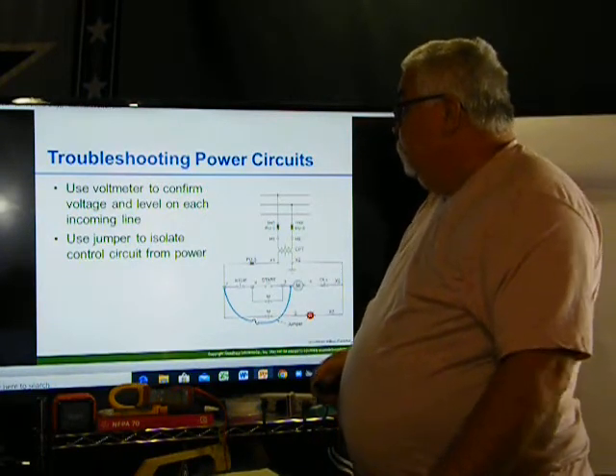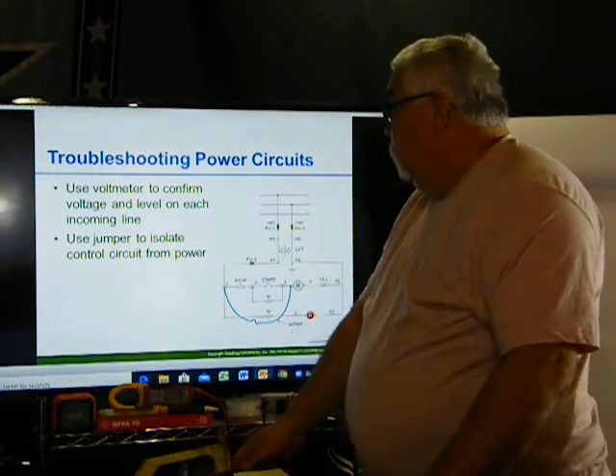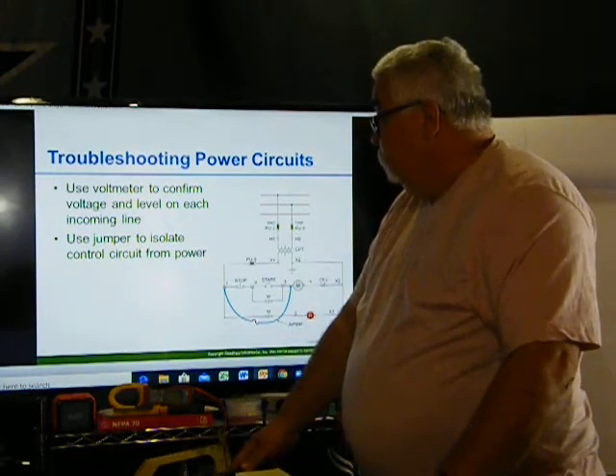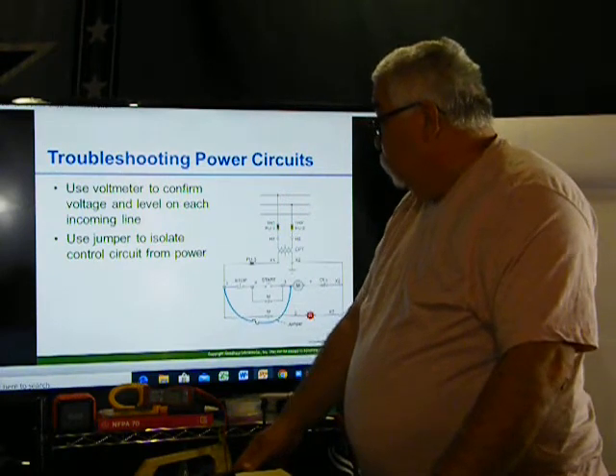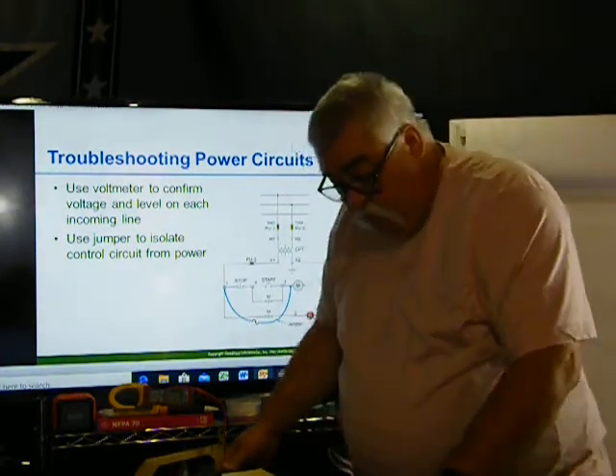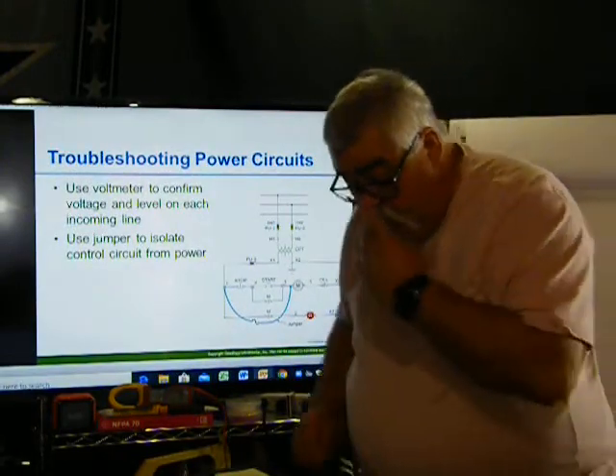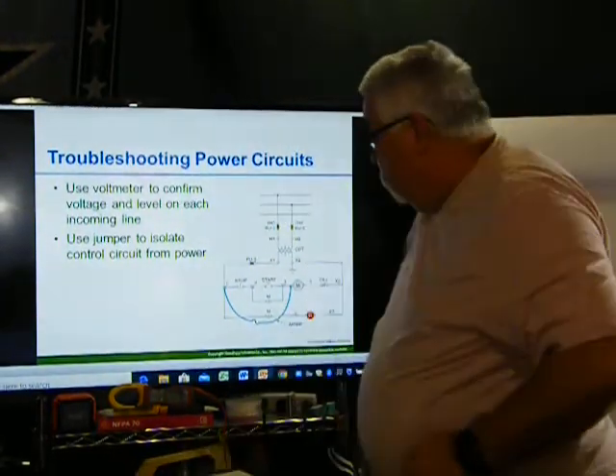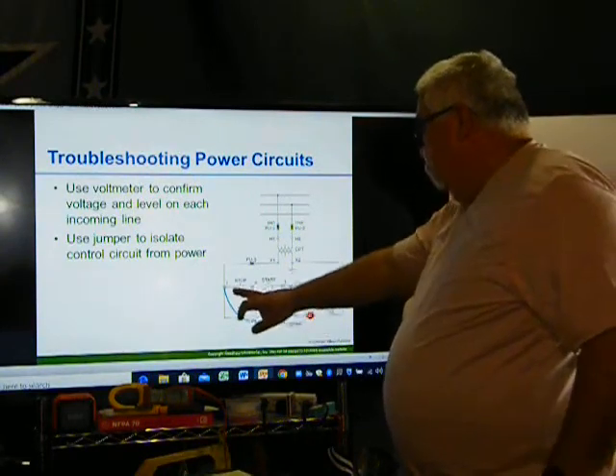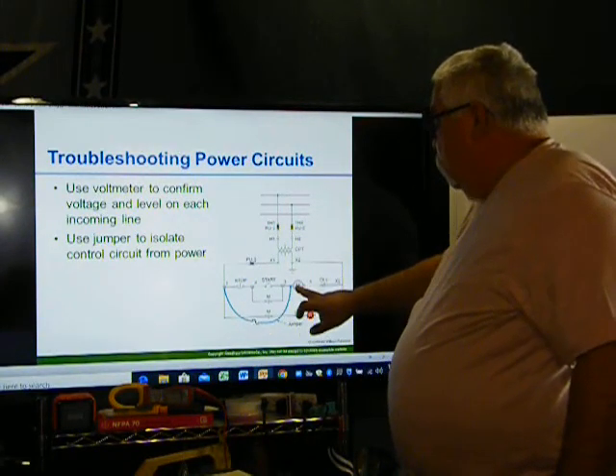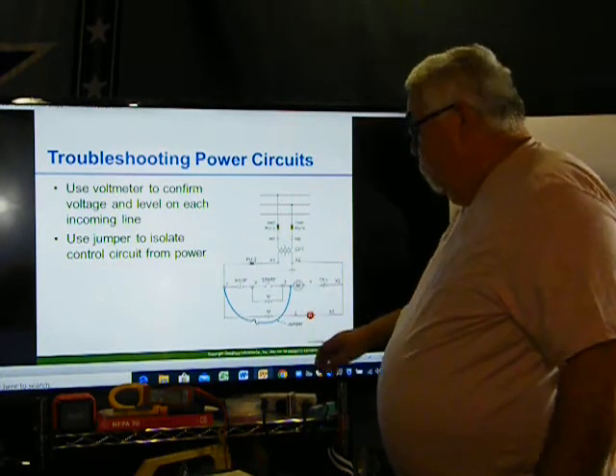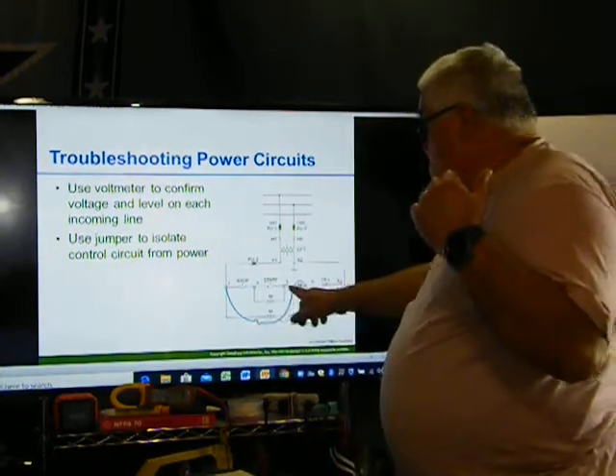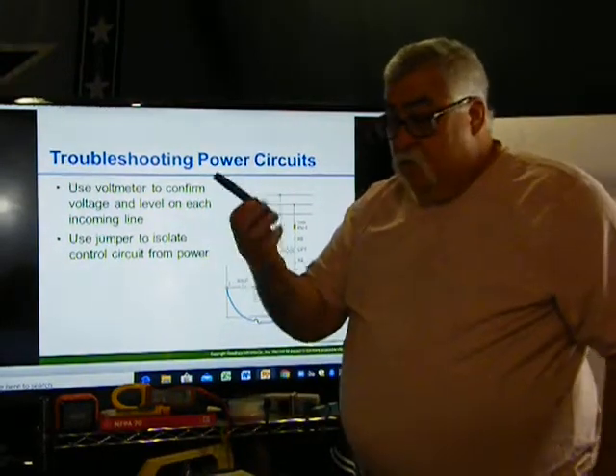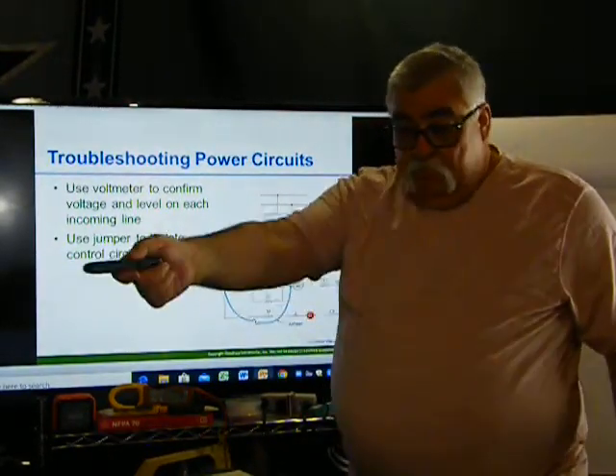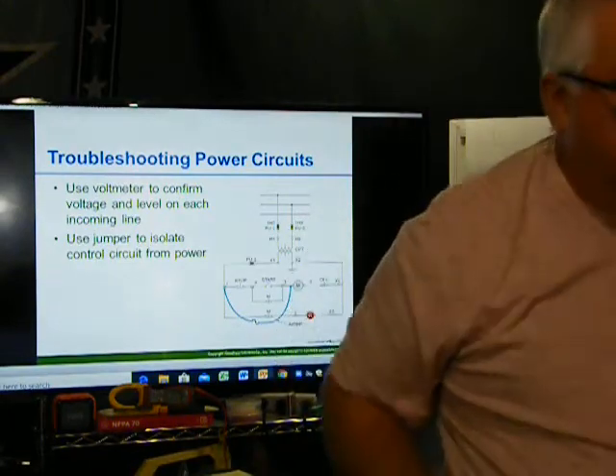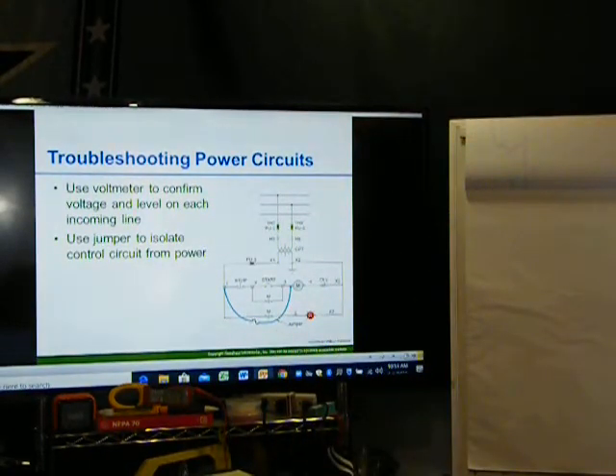It says use a voltmeter to confirm voltage and the level of each incoming line. Use a jumper to isolate the control circuit from the power. So what they're doing is they're jumpering the stop starts, and they're going straight to the contactor to close the contactor to see if the motor comes on. So they're going straight to here, or you can use a screwdriver or something and then push the contactor in.